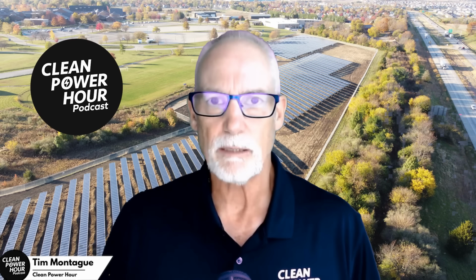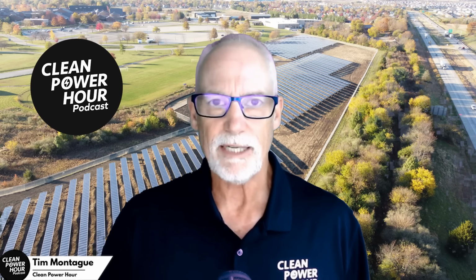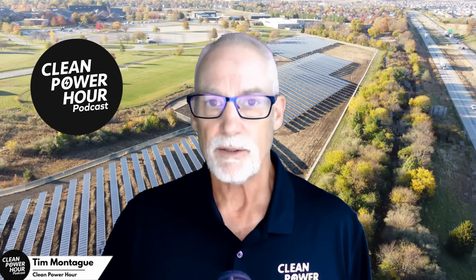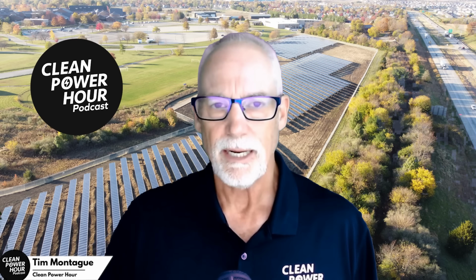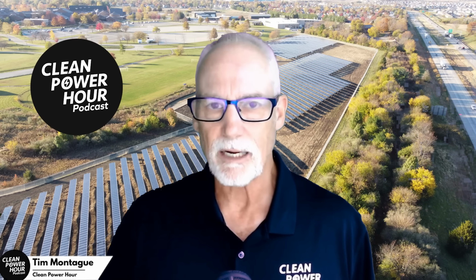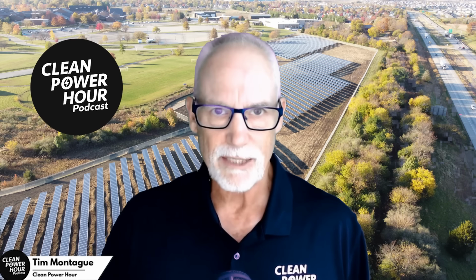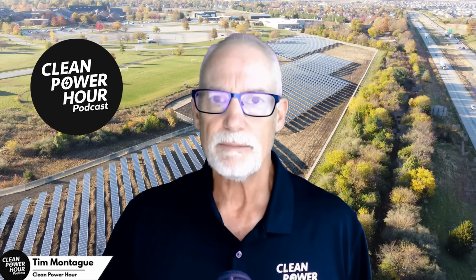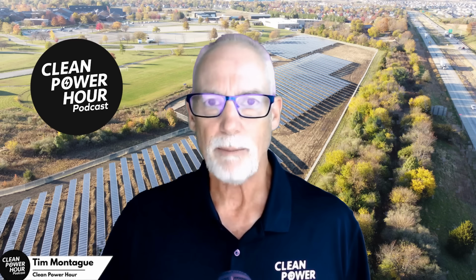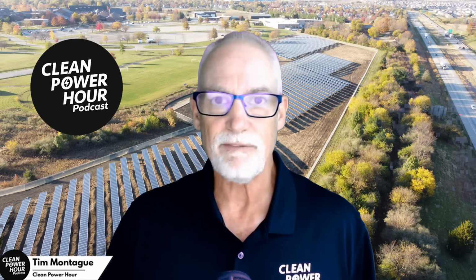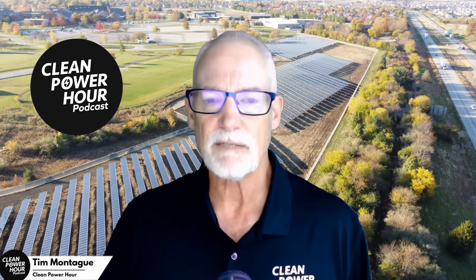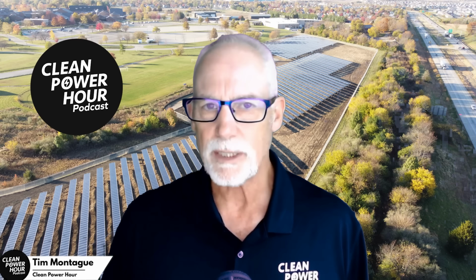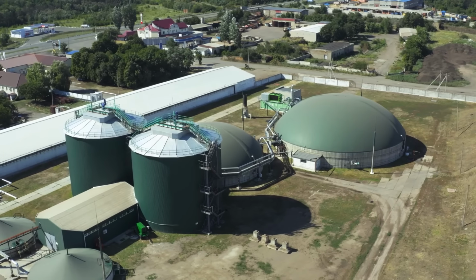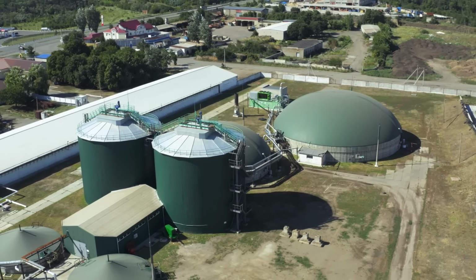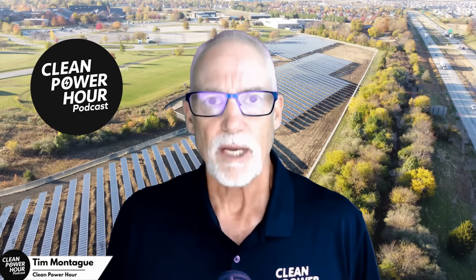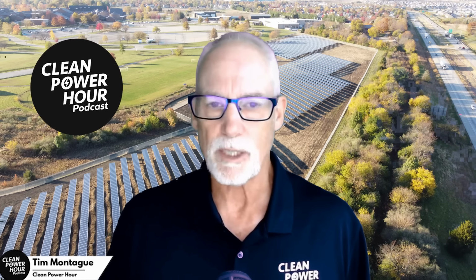Quick context on the numbers here, because I want to be precise. The air quality advantage of the linear generator is real, near net zero NOx, no particulate matter. It passes California's air district permitting out of the box. That's its genuine edge over engines and turbines. On carbon, it depends entirely on the fuel. Running on pipeline natural gas at roughly 46% net efficiency, you're looking at around 0.4 tons of CO2 per megawatt hour, roughly grid gas equivalent. Run it on dairy biogas, where you're destroying methane that would otherwise vent, and the project can actually go net negative. So air quality is the headline, carbon is a fuel question.